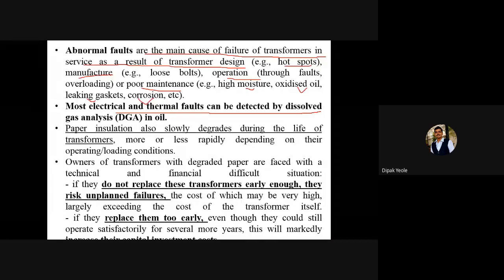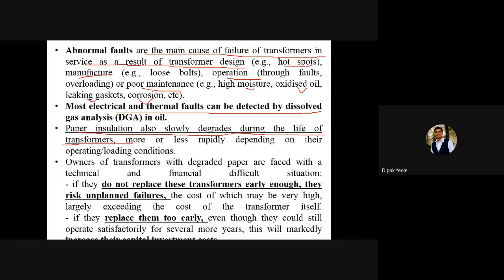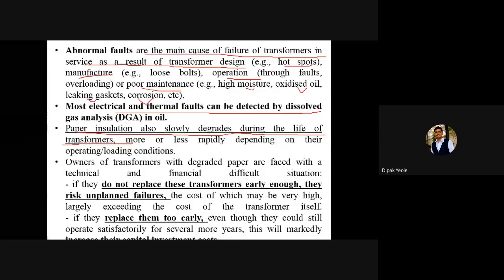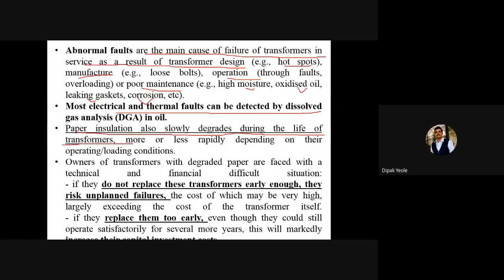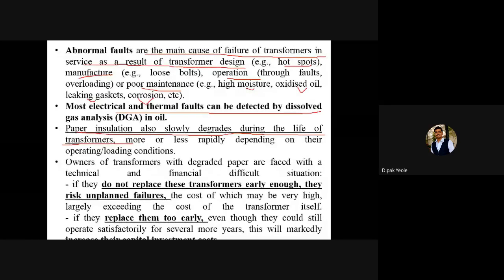The paper insulation also slowly degrades during the life of the transformer. It degrades more or less rapidly depending on operating and loading conditions. Obviously the stress will affect the insulator, and because of the degradation there can be a possibility of gases being produced. Owners of transformers with degraded paper are faced with a technical and financial difficult situation. If they do not replace these transformers early enough, they risk unplanned failures.